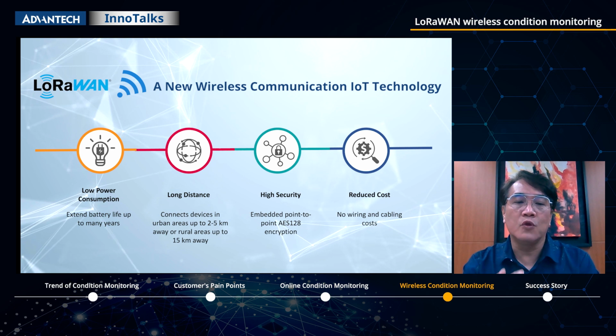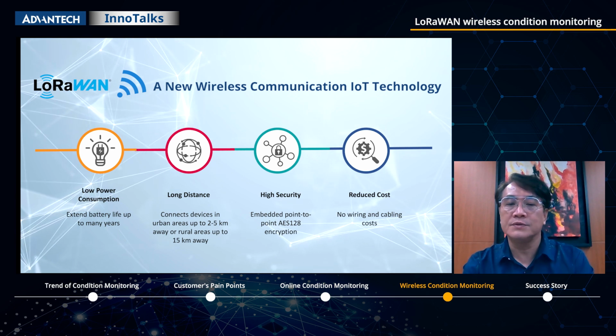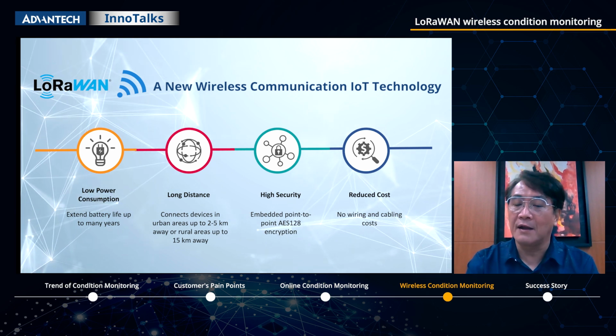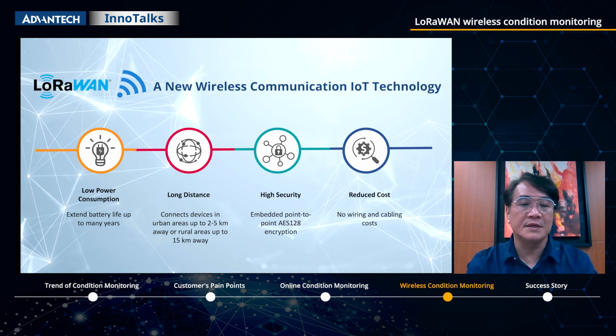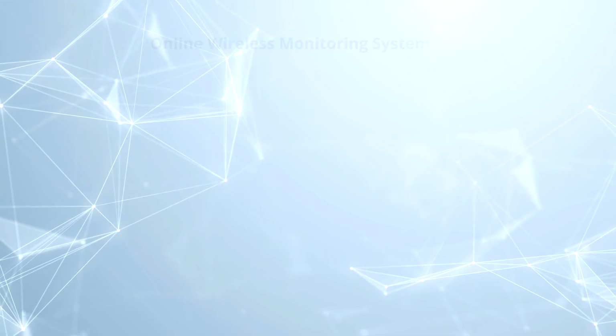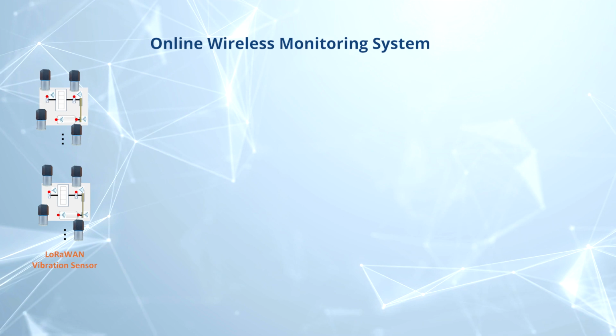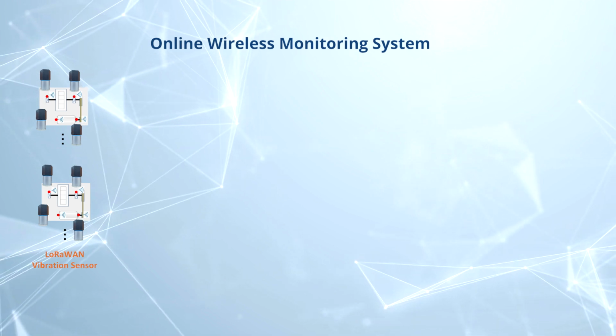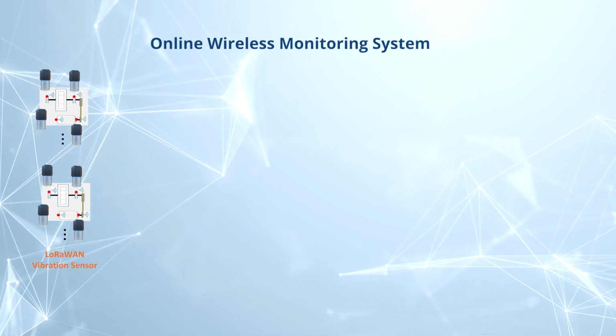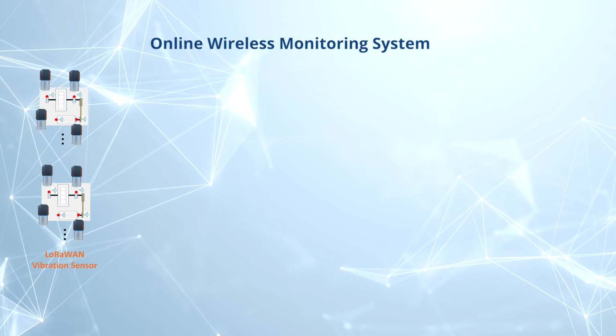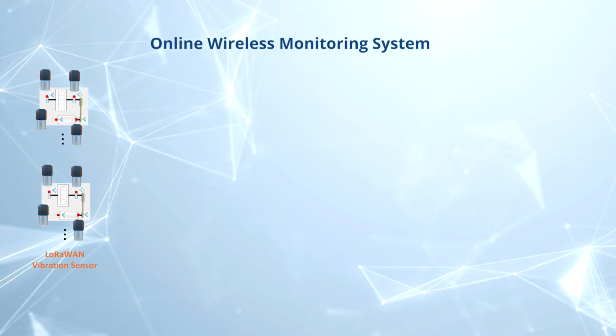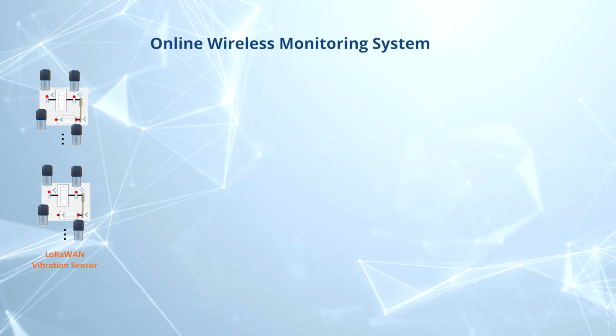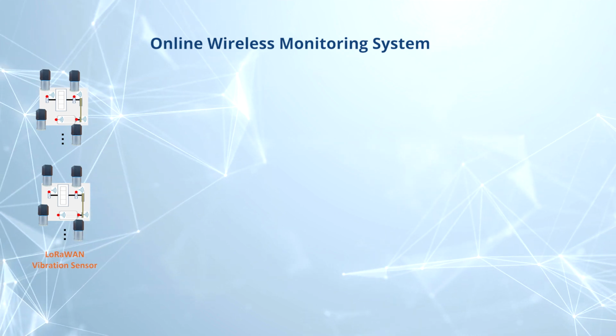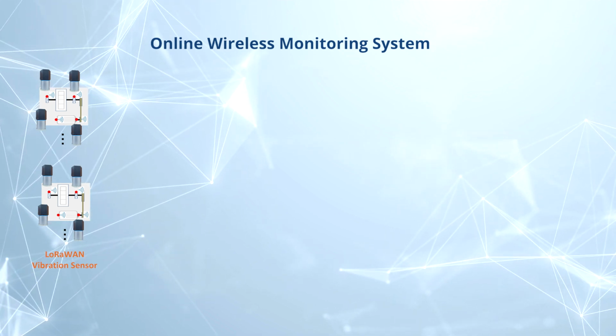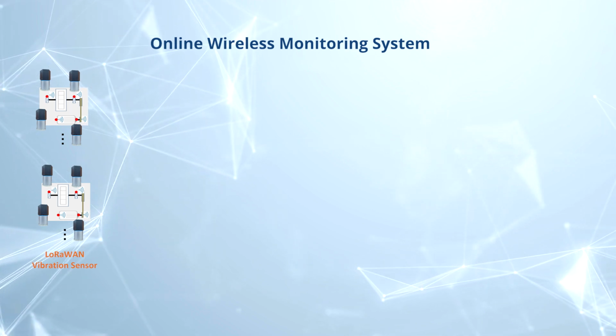Now let's take a look at how we use a LoRaWAN device in an online wireless monitoring system. A wireless instrument is installed with the LoRaWAN sensor to measure the vibration value of the machine, and the vibration is converted into a digital signal directly in the instrument.